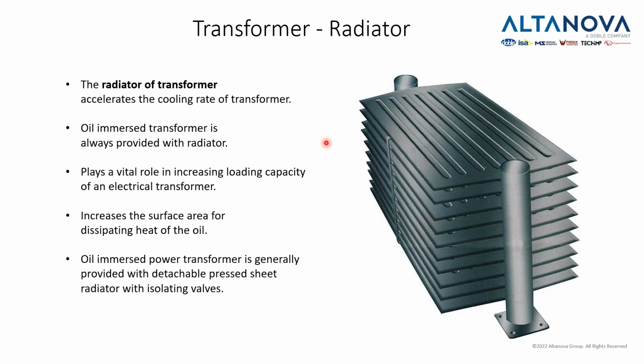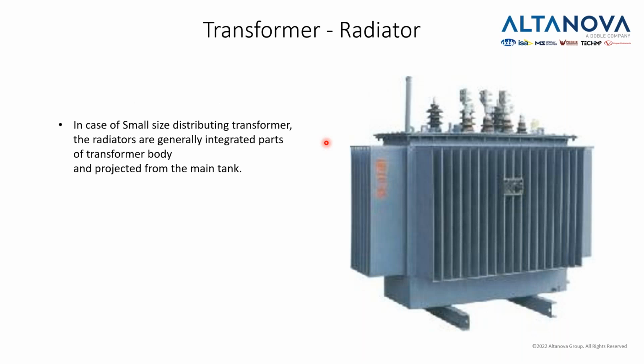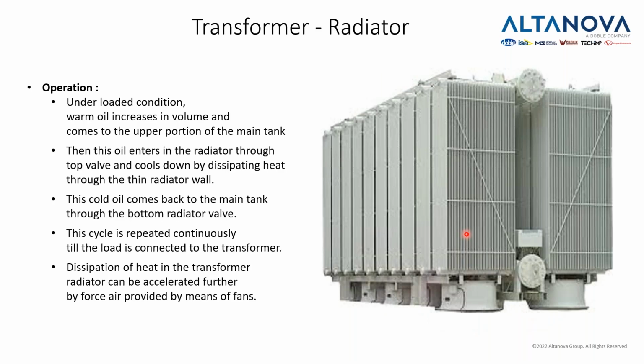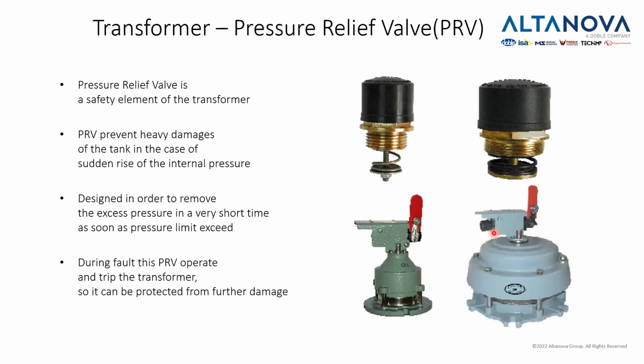Apart from bushings, we have the radiator, a very important part which is used to cool down the transformer. As the transformer works, it is super efficient, but it's not ideal. Some of the energy which goes into the transformer is transformed into heat, and that heat needs to be dissipated. So we use radiators to dissipate that heat. The radiators can be in the form of ribs on the transformer or on the tank itself, or they can be separate, like this one, for transformers which have very big power. Effectively, you might say that the cooling or the radiator can very much define the power that the transformer can sustain. And then we have some valves, some pressure relief valves.